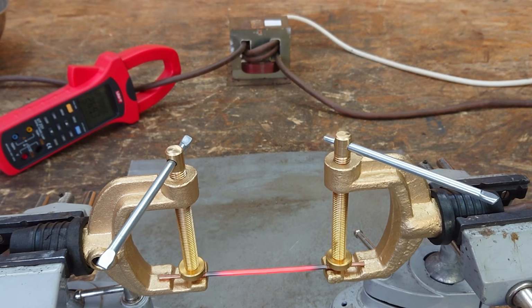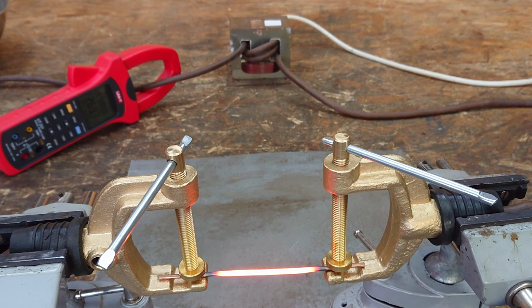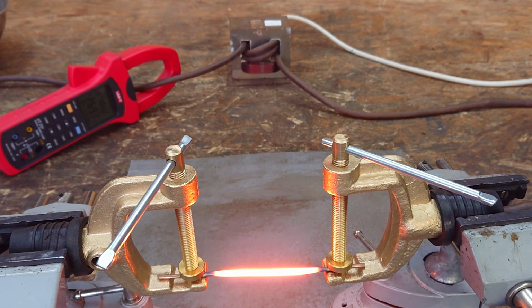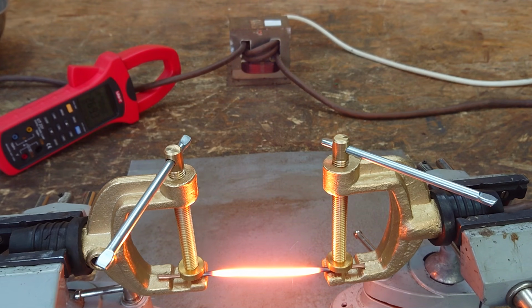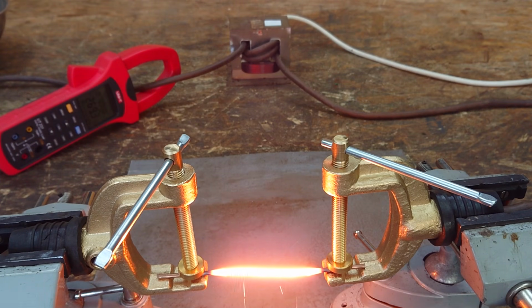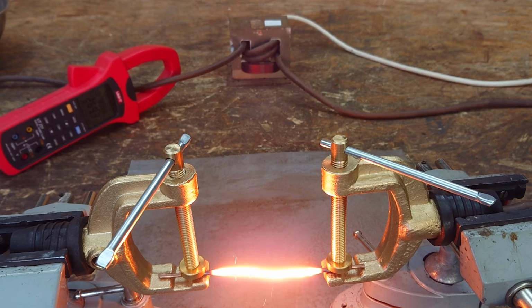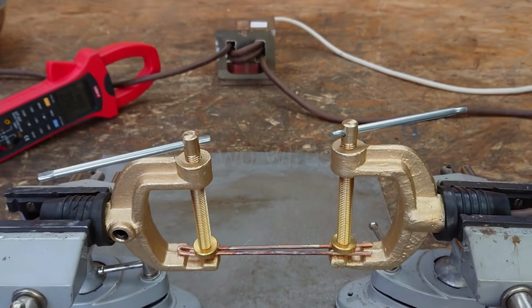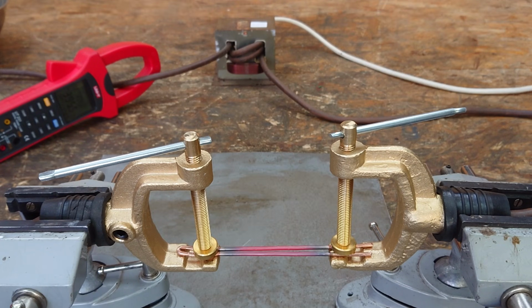The smallest transformer needs a really long time to heat up even a single welding rod, until it eventually melts and interrupts the circuit. In this case we measured 269 amps. The clamp meter is set to store the highest current measured during the entire experiment. At 2 welding rods in parallel, we've already reached the maximum we can do here.